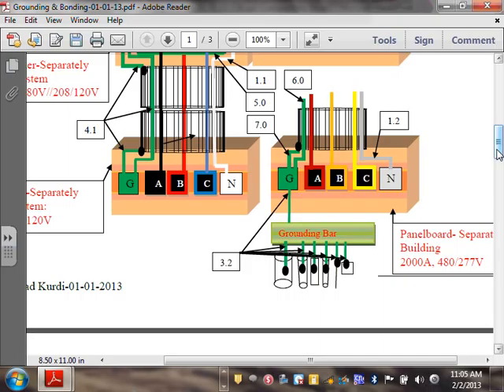Then, the only difference in the second building, guys, is that the code says you have to establish a new grounding electrode system at the second building. That's different, right? You have to have a new grounding electrode system. Because it's a big system, I have a grounding bar here, a copper bar, in the switchgear room. Same thing, I have to go to my water pipe, to my rod, to steel, to the wire, the ring, into the plate. All the grounding electrodes that exist in the second building must be bonded together. But how many do you need? You only need 1. You only need 1.